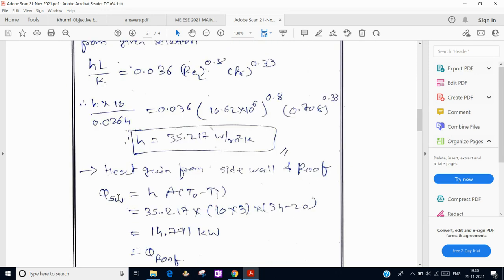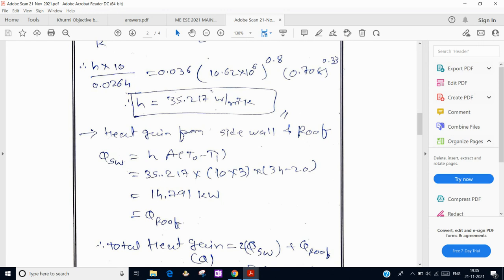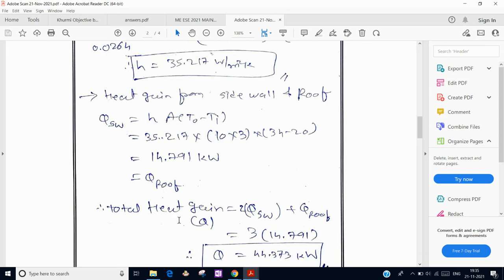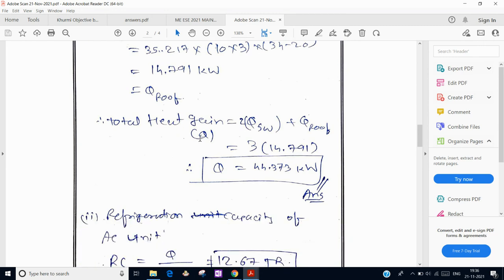Heat transfer from one sidewall is Q = h × ΔT × A, where ΔT = 34 − 20 = 14°C, length = 10 m, and width/height = 3 m. This gives 14.791 kW per surface. The total heat gain is 3 × 14.791 kW — two sidewalls (left and right) plus one roof — giving a total heat gain of 44.373 kW.